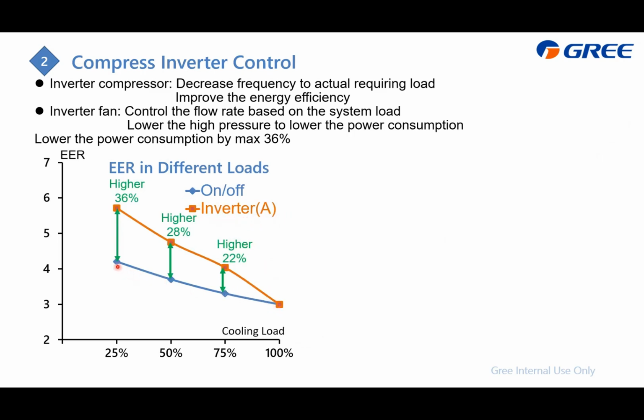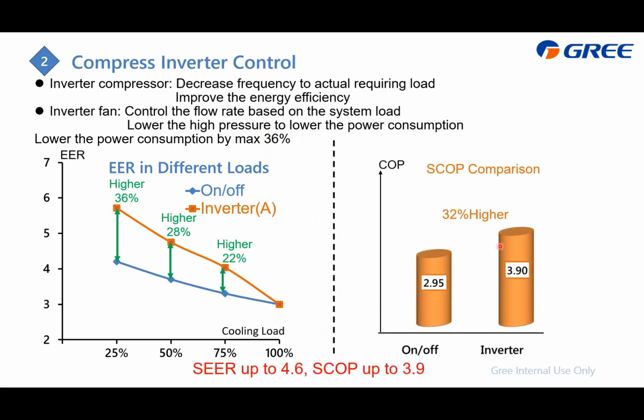And you can find it for the cooling capacity. The blue line is the on-off, and the orange line is the inverter. You can find that at 100% load, it is the same. And if the load is lower, for the inverter the efficiency, which is the EER, can be higher, by up to a maximum of 36%. And not only the cooling, but also the SCOP for the heating performance, we can get 32% higher in general. So here is a summary: for the SEER we can reach as high as 4.6, and for SCOP it can be up to 3.9.